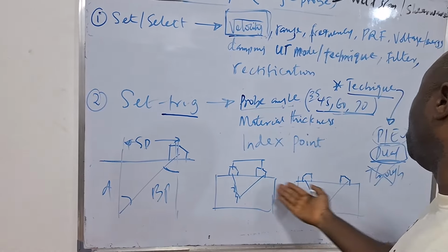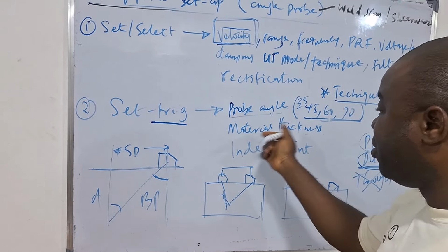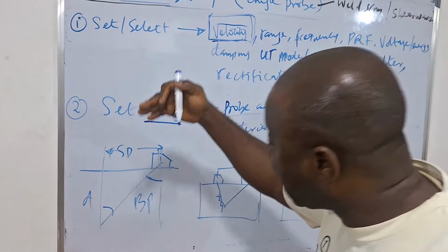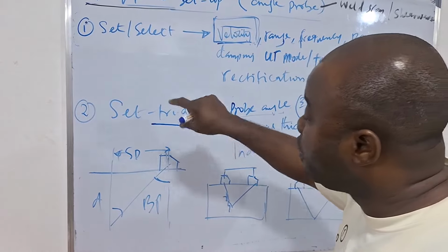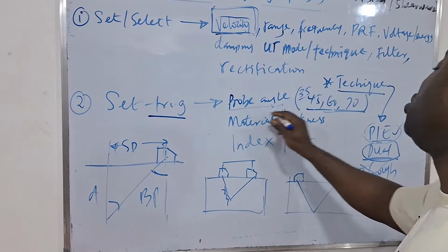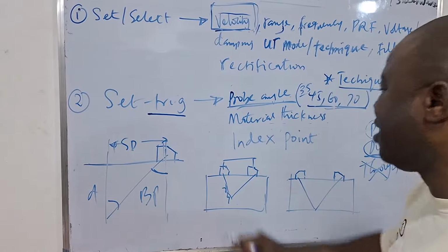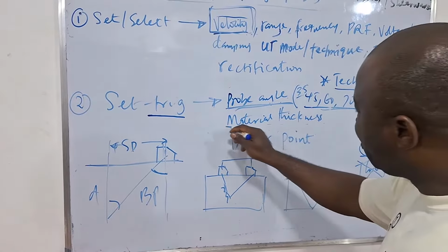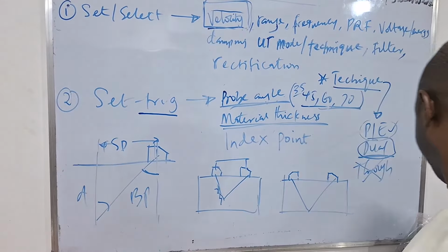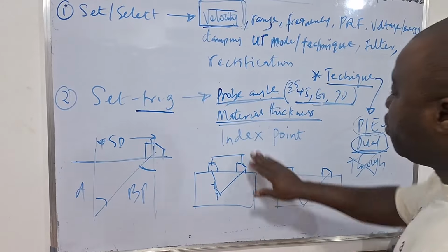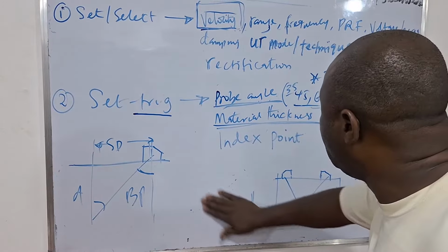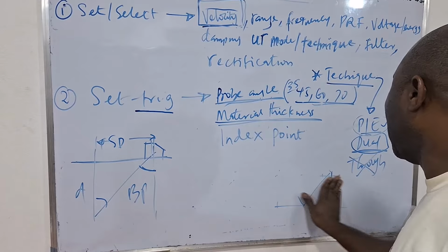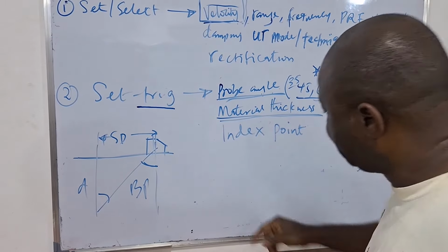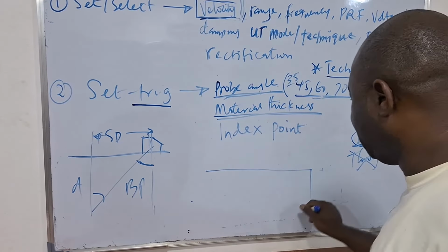Even when you do your indexing and all that, as long as your angle is wrong, you are going to be getting wrong values. So you need to select the correct angle. The next important thing you need to set, which is very, very key for your angle probe, is your material thickness. And if you look at your units, the same idea.